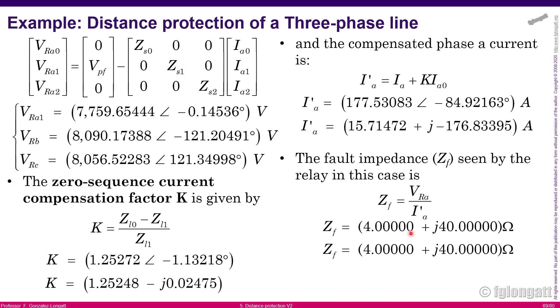To summarize: with this numerical example, I have demonstrated that by using the proper equations and relationships between voltages and currents for each fault type — three-phase, line-to-line, and phase-to-ground — we can make the distance relay measure the positive sequence impedance of the transmission line in all cases. This is very important because we use the positive sequence impedance to define the settings of the distance relay.